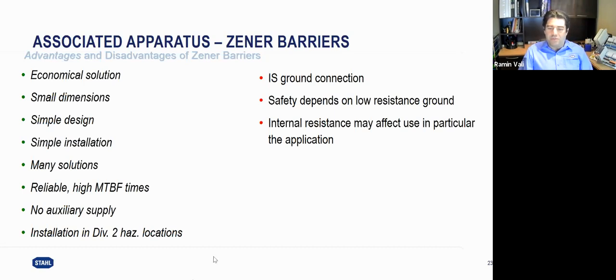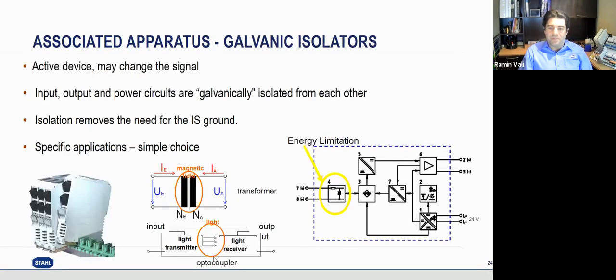Now, another solution for that is using the isolator. Basically, isolators use the same concept, but they have a transformer to separate primary from the secondary. And that means we don't need to have a ground which is connected from the safe area to the classified area. The idea is the same, because the energy will be discharged. The energy will not be propagated to the field, but it doesn't have to go to the clean ground. This is an active device because of the transformer, so we need a separate power supply for it.